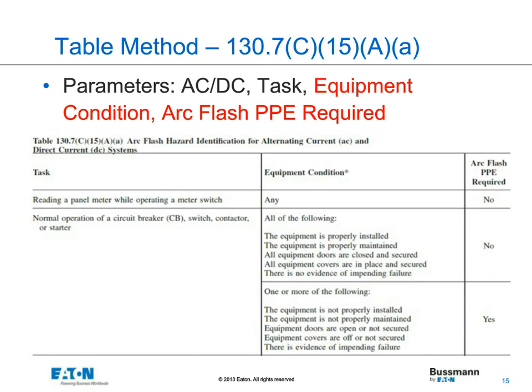Moving into the table method, we can either do an analysis or use the PPE category method. If we do use the PPE category method, we did add a new table here. Looking at this, you have some parameters for this table. It could be either an AC or a DC application. There's a task involved, and then the next column takes into consideration the equipment conditions. Based upon how you answer those questions, it'll tell you whether you need arc flash PPE or not.